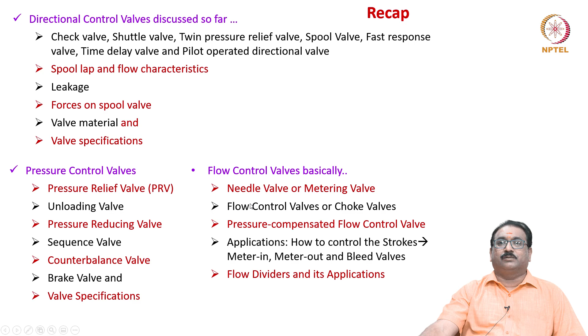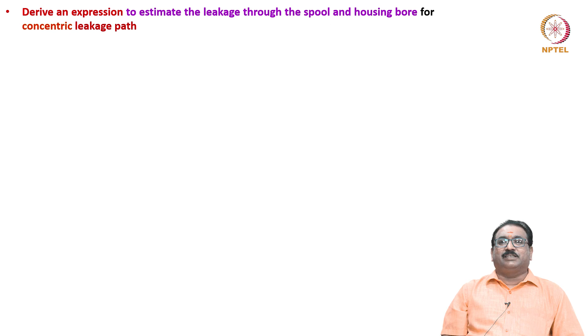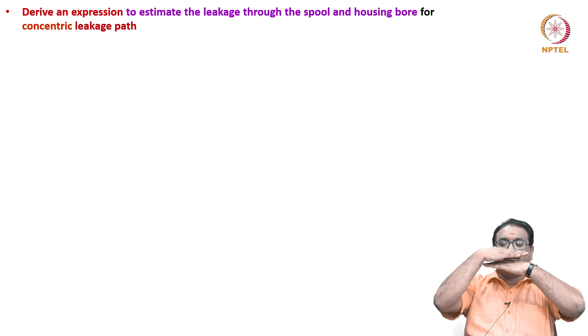Mainly, as I have told you, derive an expression to estimate the leakage through the spool and the housing bore for a concentric leakage path. What is the meaning here? You will see here the spool is concentrically mounted in the bore, meaning flow will take place through the gap. Generally, this is treated as flow through parallel plates. In hydrostatic elements, they derive the flow through the gap, meaning the radial clearance. Now I am deriving this using a very simple figure.